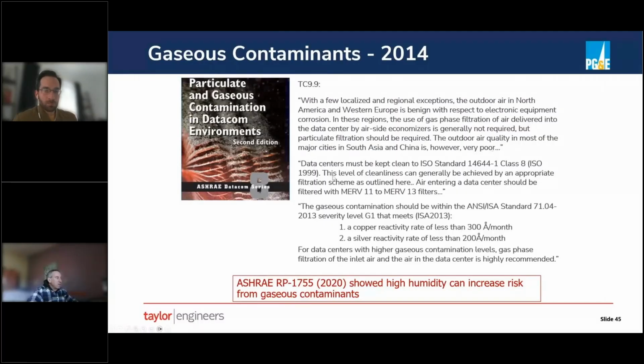And they are basically still recommending that every data center, or at least ones that have this concern, have contaminant monitoring using copper and silver coupons. They stipulate reactivity rates that would tell you that if your reactivity rate is above this many angstroms per month for copper or this many angstroms per month for silver, you have some risk and you should be thinking about gas phase filtration. I am not aware of any data centers that actually have gas phase monitoring or filtration.